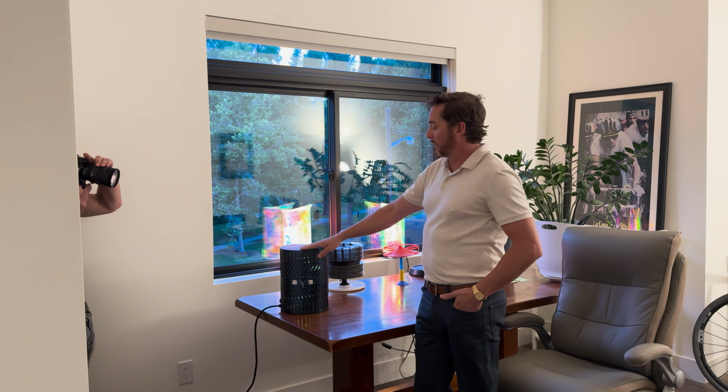That's a ceiling fan, same fans we use today, same fans that are propellers on our aircraft. The third type of fan is called a centrifugal fan, as we know, where as you rotate a stack of fan blades, these would typically be fan blades oriented vertically, you're taking in suction through the center and you're putting out pressurized discharge. This is very important because these are the same fans that are in our hair dryers, these are the same fans that are in our vacuum cleaners, and they're able to take suction through a filter. So they can have a negative pressure here, and then they're able to put pressurized discharge through ductwork.